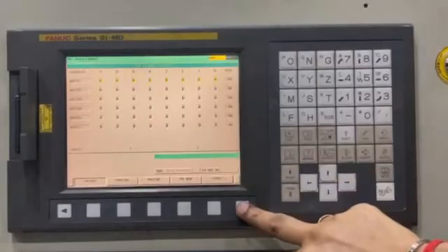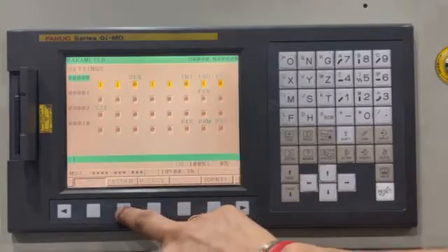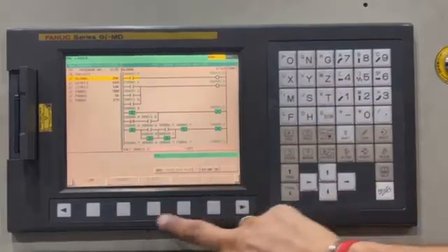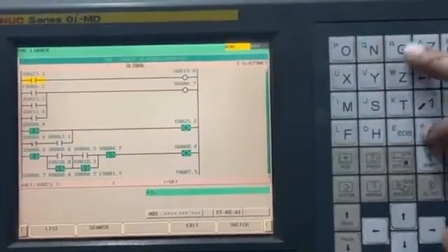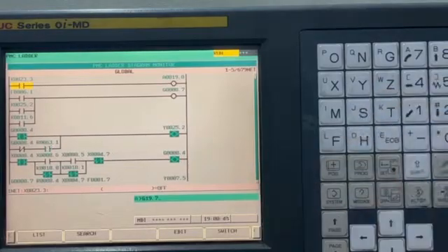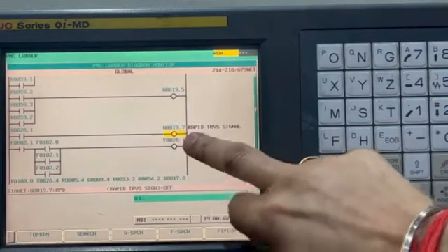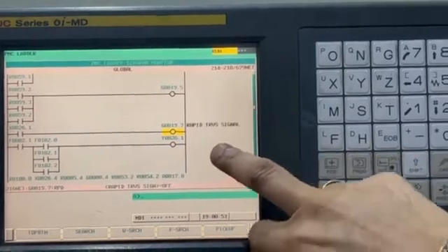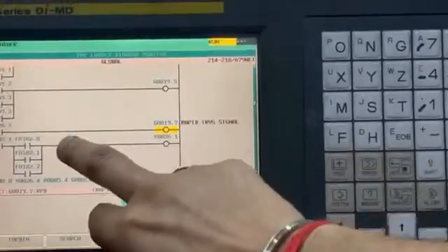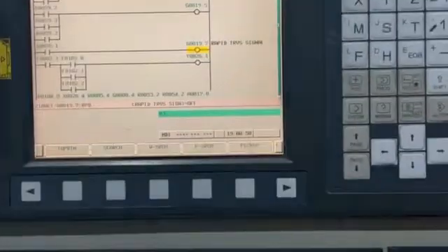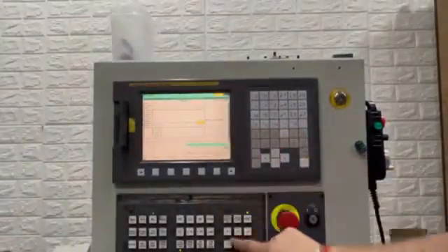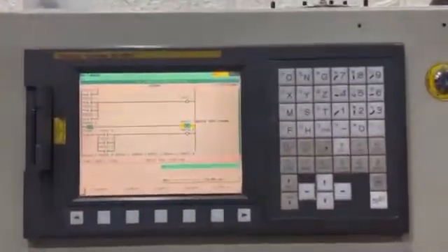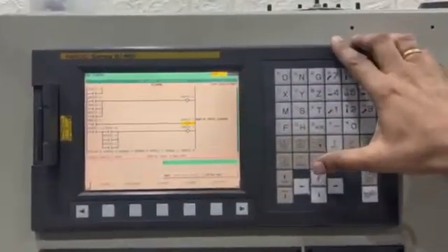In the ladder, I will show you G19.7. This is the signal G19.7. This signal gets on when X26.1 is pressed. We can see X26.1 is pressed and 19.7 is on. The moment I press it, signal is on; the moment I release it, signal is off.